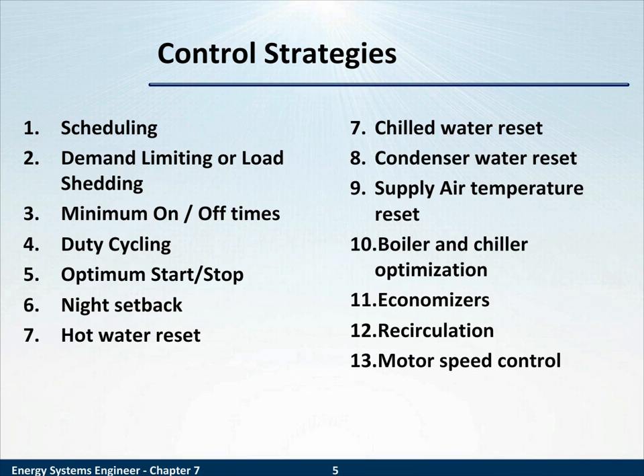Boiler and chiller optimization. Imagine if you had multiple boilers, multiple chillers, and one was much more efficient than the other. Well, aside from having somebody physically go turn one off, your control system can prioritize the most efficient optimization of your boilers and chillers. Next are the control strategies for economizers. That was our example of control strategies earlier, automatically adjusting the system so that when it makes sense for an economizer to be used, the control system uses it.